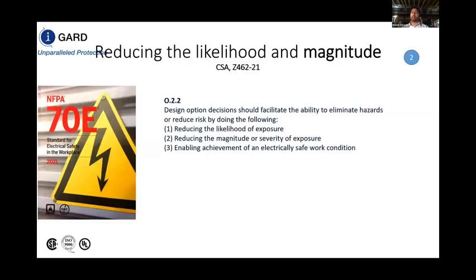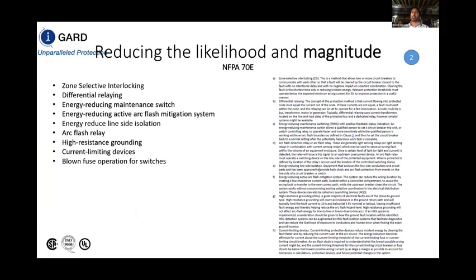Now, heading into NFPA 70E, NFPA 70E is a standard for electrical safety in the workplace and is based off the US standard. This also is mirrored for the Canadian market in CSA Z462-21. In Annex O.2.2, it says that design option decisions should facilitate the ability to eliminate hazards and reduce risk by doing the following: reducing the likelihood of exposure, reducing the magnitude or severity of exposure, and enabling achievement of an electrically safe work condition. Further to this, in Annex O.2.3, they list out 9 different incident energy reduction methods.